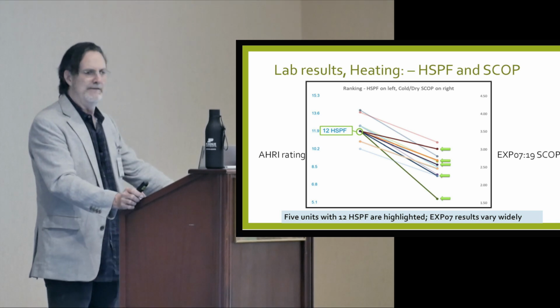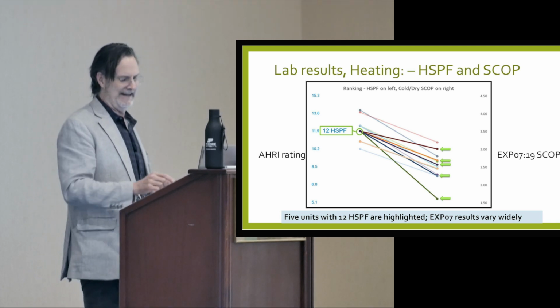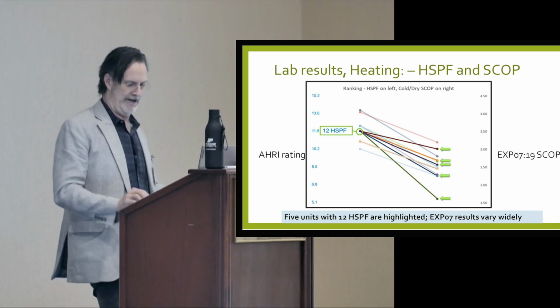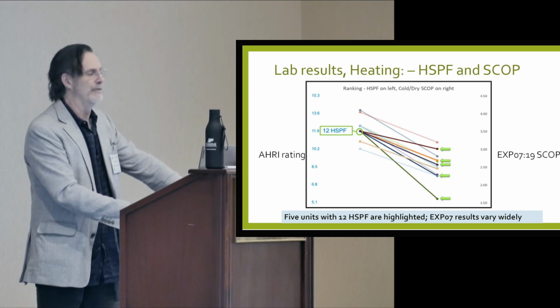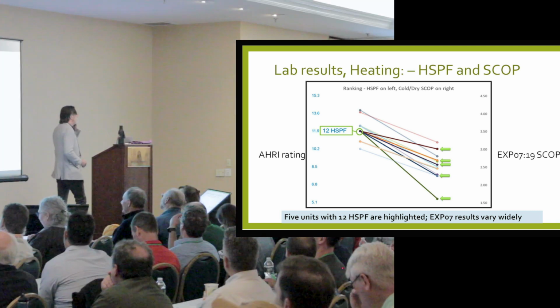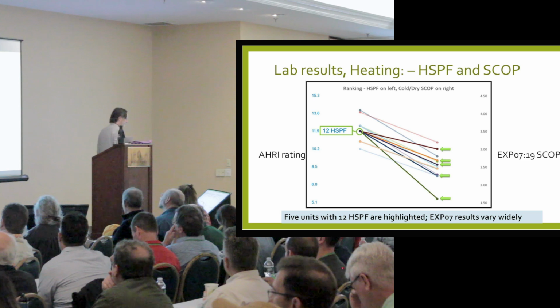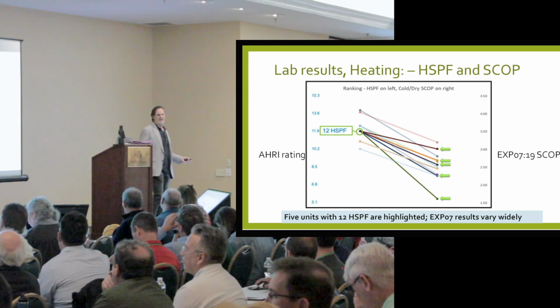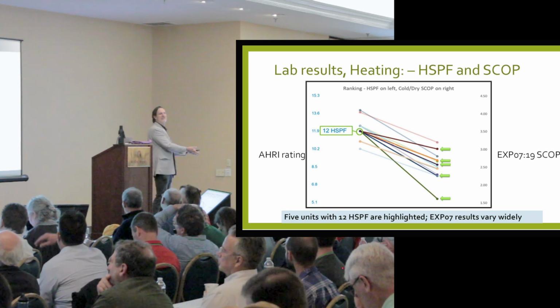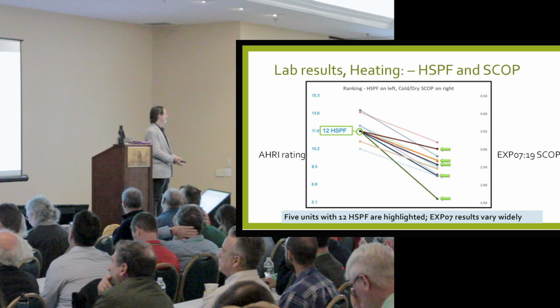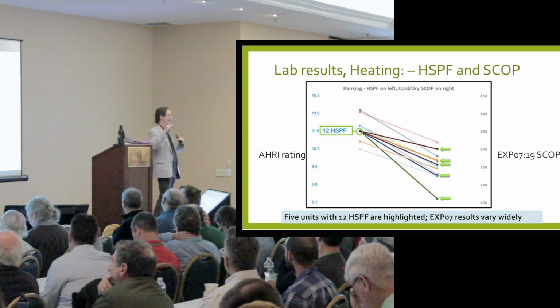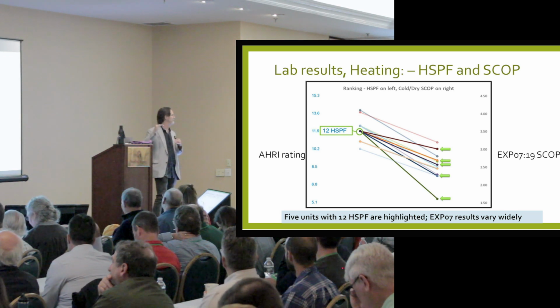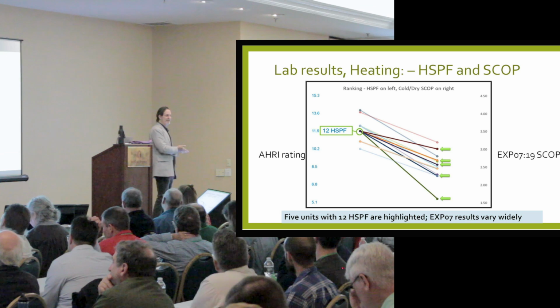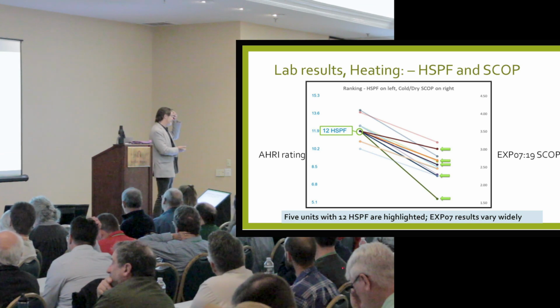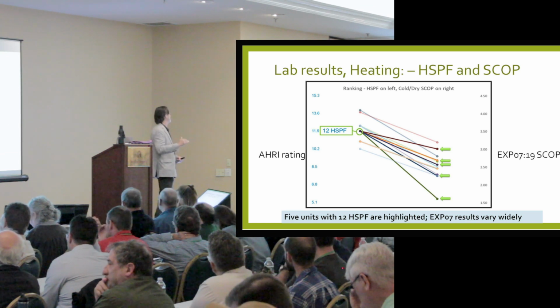And make a note of that one that's on the very bottom, because it's a little bit of an outlier, and it was not a test error. One of the first things manufacturers do is they say, well, that's the published HSPF. We didn't base that on the same unit that you tested. And we often put a little margin of safety when we publish the HSPF, because there's audit tests. And we want to make sure, so sometimes the HSPF is underreported.